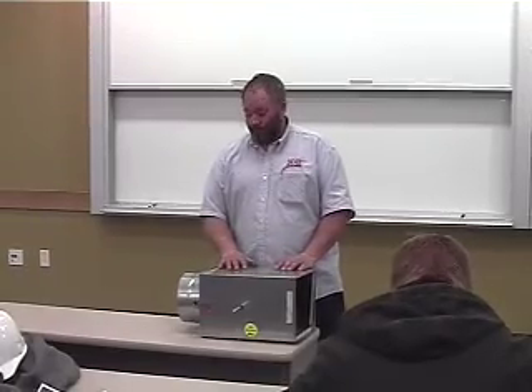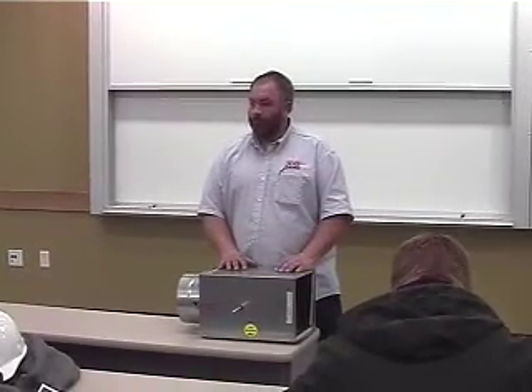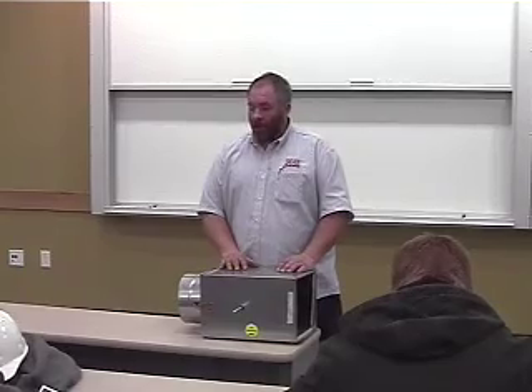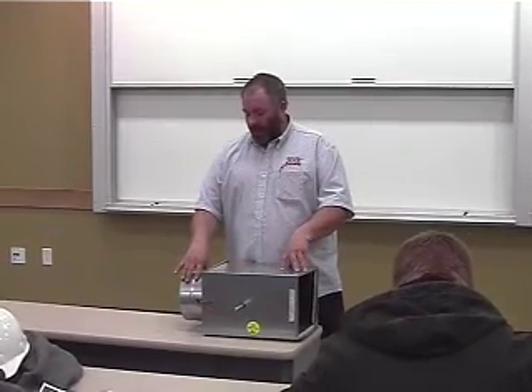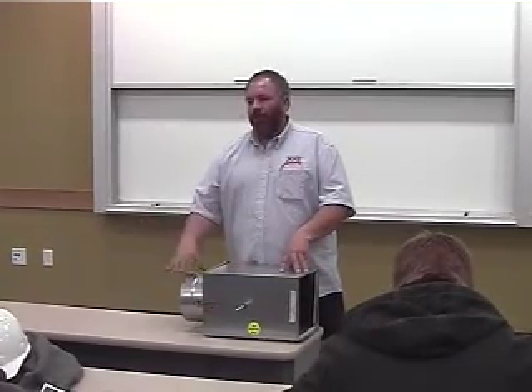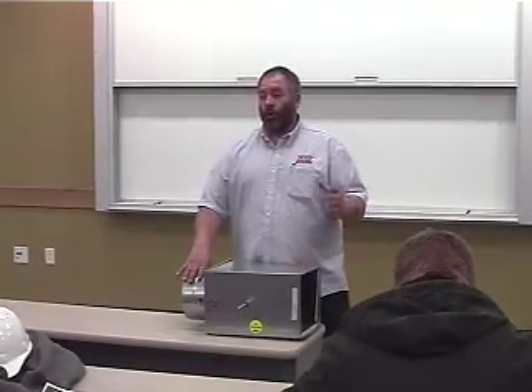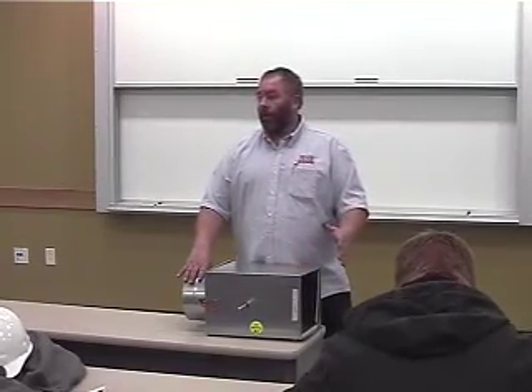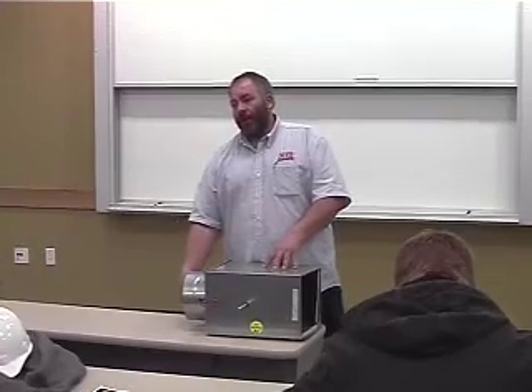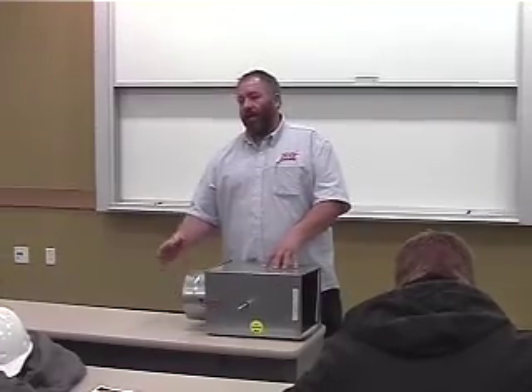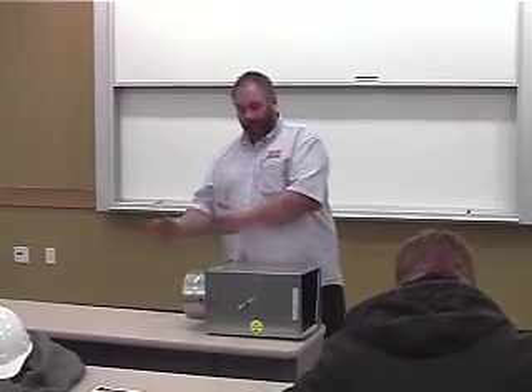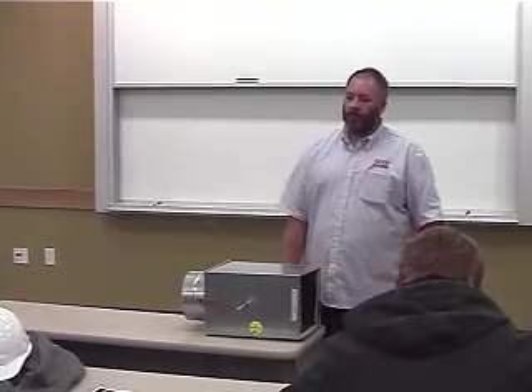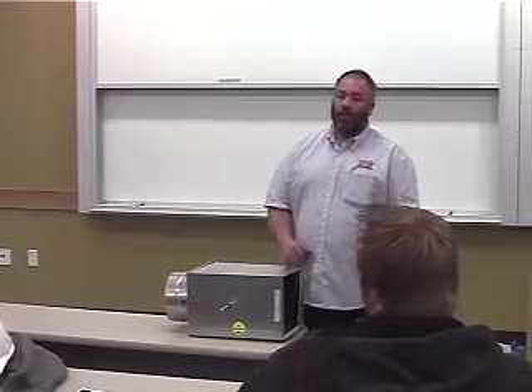Coils are before? Coil would always be after, usually. Coil will always be after. On a VAV box, or any type of box, how fast you move the air through determines how much heating or cooling ability we have in the coil. And so this is always your high pressure side. If we ever put anything here, it would take twice as thick of a coil to pick up the same amount of heat you need on this side, because your airflow is moving lower.